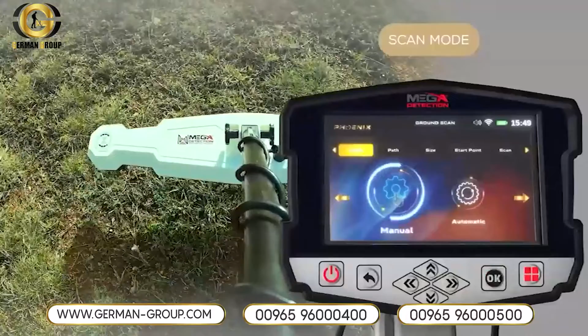Scan path. On this screen, the user can specify the direction of the scanning path, which includes two options. 1. One direction. The ground scan is performed for each line with the same direction, i.e., the direction of the scan is according to parallel lines and a distance between them. 2. Zigzag. In this case, the start of the next scan line is at the end of the previous scan line, while leaving an offset distance, meaning that every 2 successive lines are scanned in an opposite direction. Select your preferred scan path mode using the left-right arrow buttons, then press the OK button.